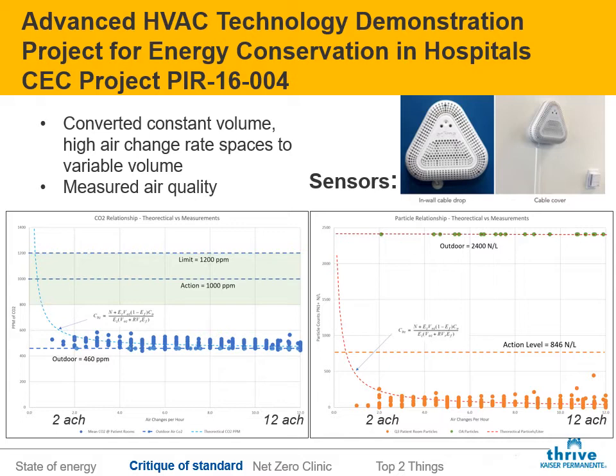And that's the same with air quality. We don't really need a whole ton of air for hygiene ventilation. 15 CFM per person or 20 CFM per person comes out to a half an air change or maybe 1 air change. That's all you need for contaminant control and air quality. And so we often need 6 or 10 or 12 for cooling, but it's not really making things a whole bunch cleaner.